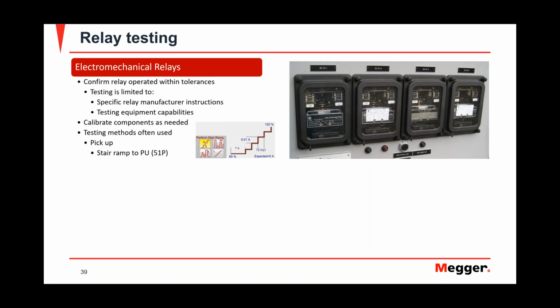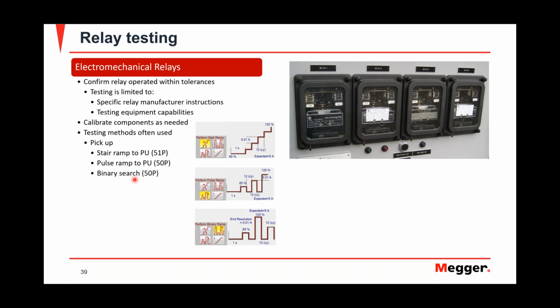The testing methods often used for pickup, you could have just a regular staircase or ramp tool. You could do a pulse ramp in which you increase your current little by little, but you shut it off. There's intervals where there is no current going into the relay. That way you don't overheat the relay. You will use that to test an instantaneous. Binary search. This is a good tool when you don't know what the pickup of an instantaneous is or any pickup whatsoever. This binary search tool, you only have to give it a band, a big band where you think the pickup is, and then the tool itself will know when the relay should trip and should not trip, and it will narrow it down to find the actual pickup. So those are 3 tools that you could use to do your pickup.